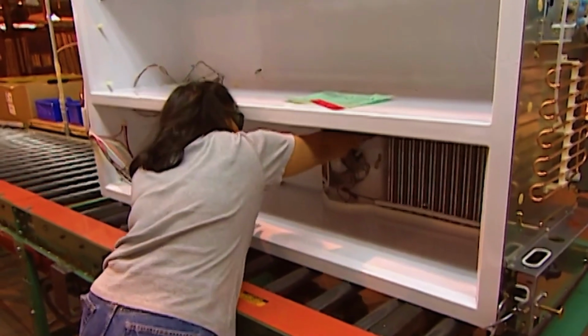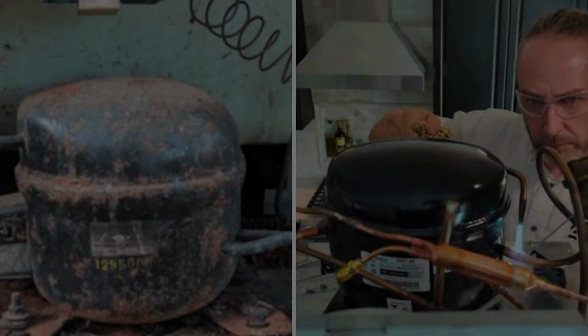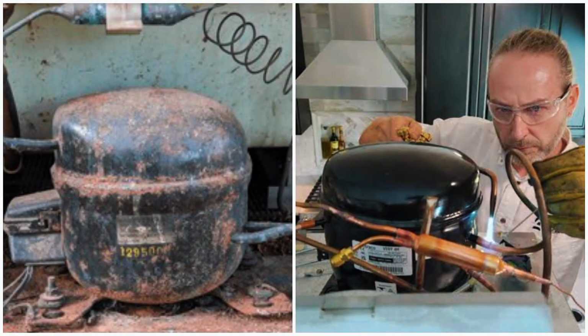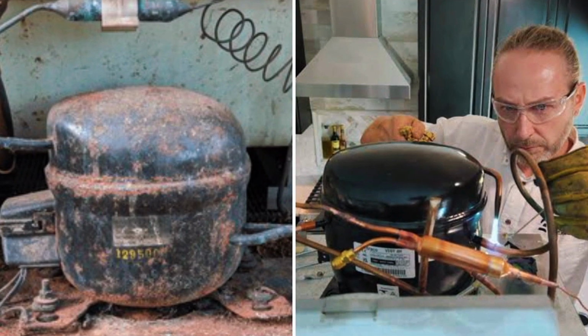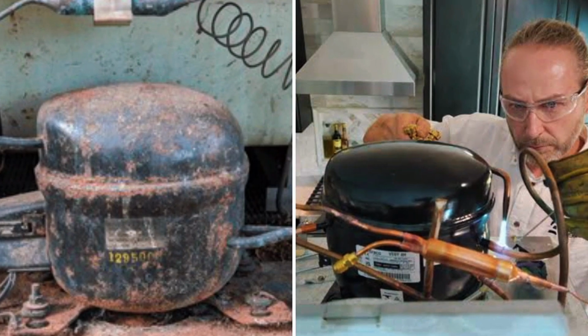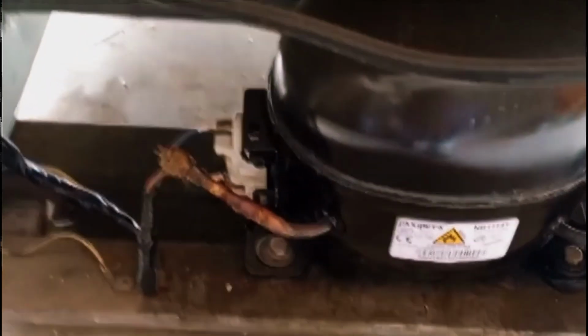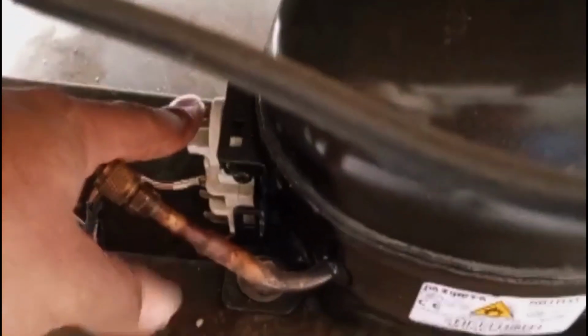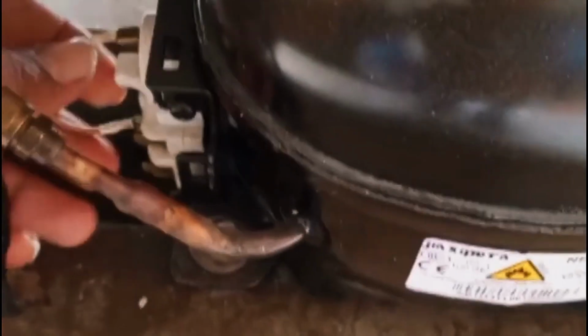When a compressor dies, it can fail clean, or it can fail dirty, and a dirty failure means internal wear has sent metal debris circulating through the entire sealed system. Now, the job is not a simple part swap, because you are looking at flushing the lines, pulling a vacuum, and replacing filter dryers, while hoping the new unit does not die young from whatever junk stayed in the lines.